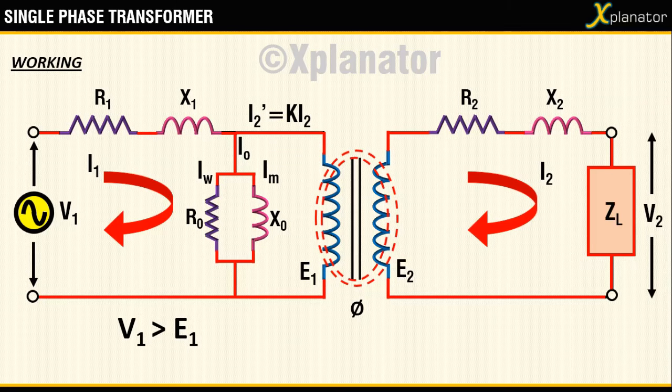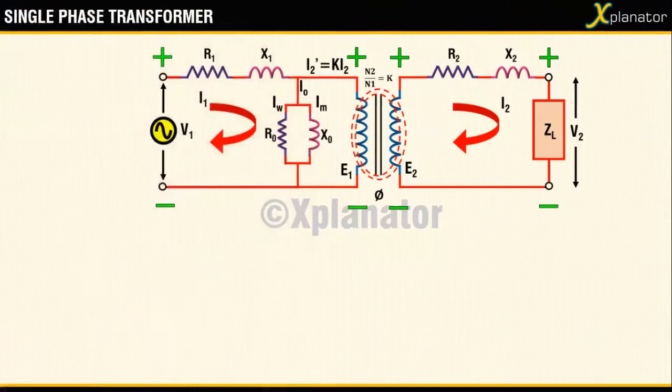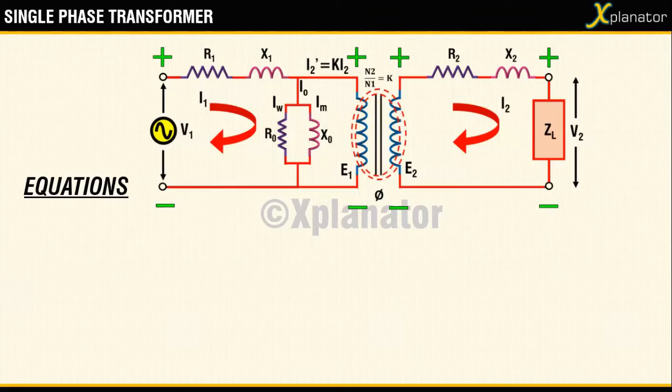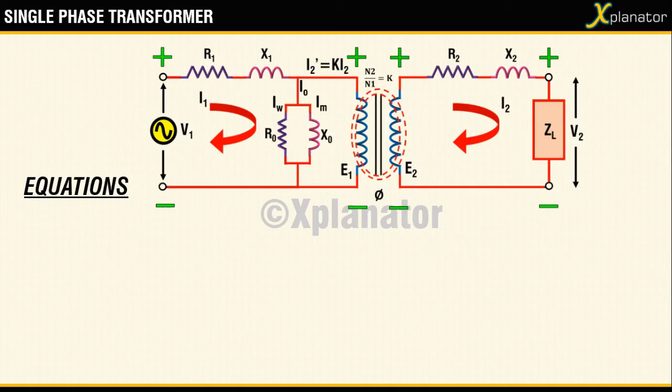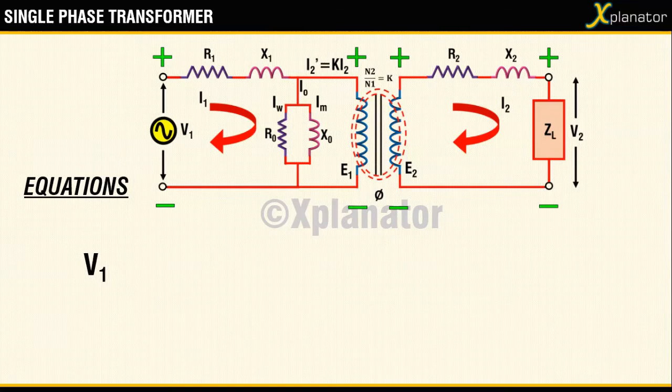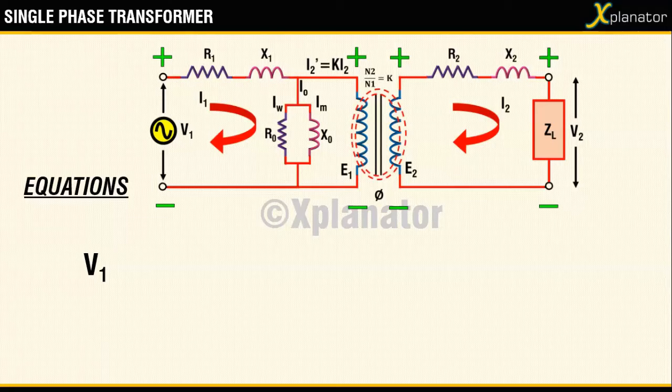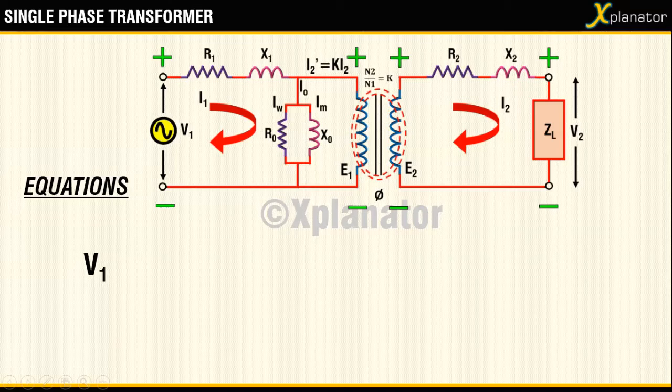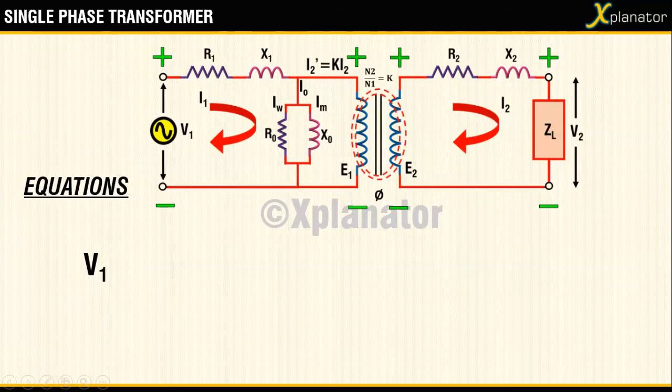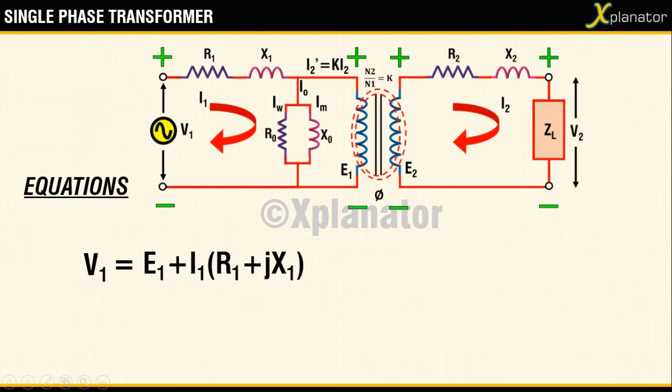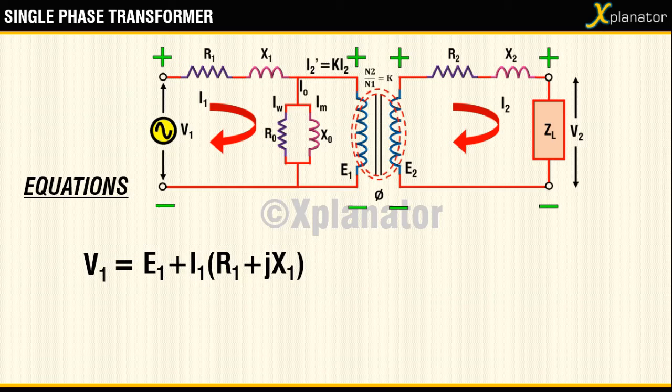Considering these parameters we can write the equations for input voltage V1 and output voltage drop V2. The input voltage in the primary circuit, that is V1, has to overcome the back emf E1 as well as the voltage drop across R1 and X1. So the equation may be written as V1 equal to E1 plus I1 into R1 plus J times X1.